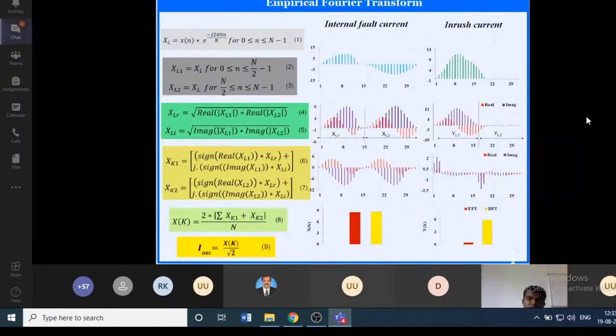While multiplying, if you have the signal of inrush current, we have the peak in one half cycle and the remaining is almost 0. So while multiplying, the resultant will be 0. That is the beauty of this transformation technique. We have developed it based on experience. So what is required to detect the inrush current? If it is an internal fault, there are both positive and negative parts.